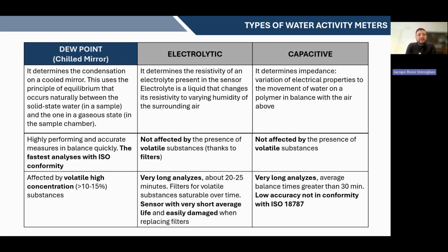Currently, in the market, there are mainly three different kinds of sensor. And in both cases, these sensors have a weak point, and also some strengths. The dew point, the chilled mirror, is the one that grants you conformity to the ISO at the same time with the fastest analysis, because we are talking about 4 to 5 minutes to run a test.